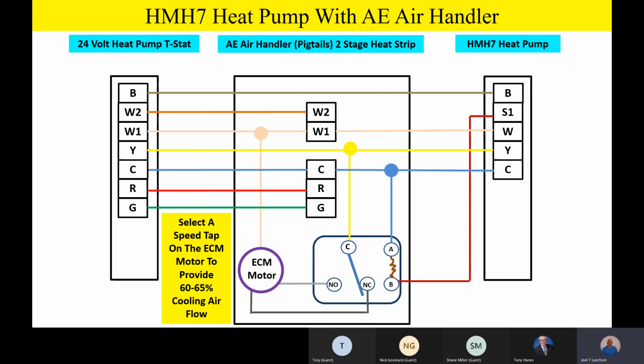Depending on the area of the country, if you're in a real humid environment and you have to select between 70% airflow or 55% airflow, take the 55% airflow, because remember, if the airflow comes down, you have more humidity control. So just make those decisions when you get out there on site. Any questions or comments on how we're wiring up the relay and the low voltage wiring on this block diagram before we show you a quick animation of how that relay works to reduce airflow? Any questions or comments on the low voltage wiring?